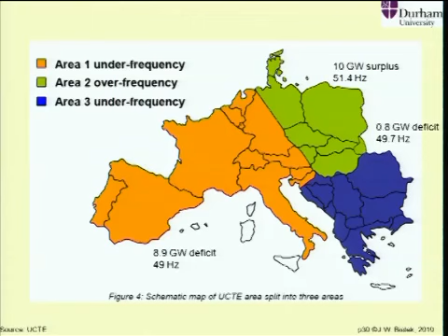So they ended up, because there was a deficit of generation, with the frequency going down to 49 hertz. In the eastern part of Europe, which was an exporter of about 10 gigawatts, because there was too much power, they ended up with too high a frequency, 51.4 hertz. And in the southeastern part of Europe, there was just a slight deficit, 0.8 gigawatt, which is not much, it is below 1 power station. So the frequency dropped to just slightly below 50 hertz. So there was not much happening. So the main problem was in Western Europe, how to maintain security of supply with such a huge deficit of generation, and how to contain things going wrong in Eastern Europe, because there was too much generation.